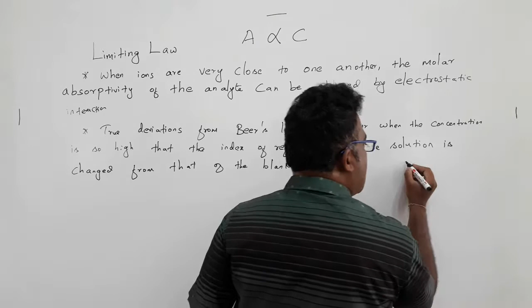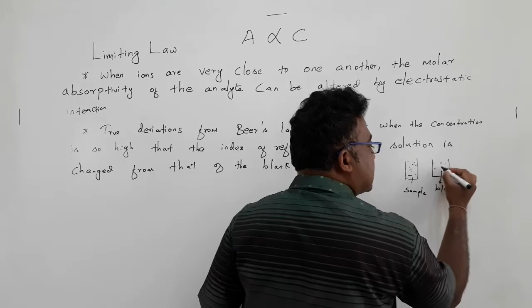When you are going to measure with a UV visible spectrophotometer, you have two cuvettes. One cuvette having sample, another cuvette having blank. Blank means it contains only solvent. Most of the cases solvent will be there. So it's a kind of solvent correction. How much solvent can be absorbed? That will be subtracted from the sample to get more accurate data for the absorption of the sample, which can be obtained by the solvent correction.